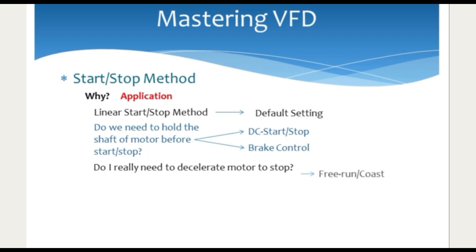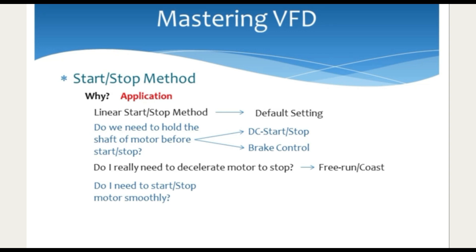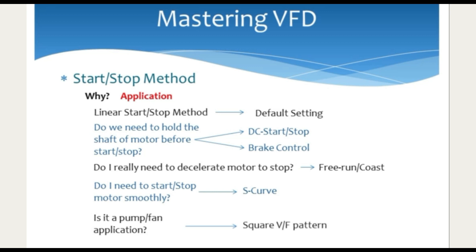Or if we need to decelerate the motor to zero speed, we select free run or coast method. For an elevator application where smooth start and smooth stop is required, we can select S-curve. If the application is a pump or fan, at low speed we may require less voltage, so we can choose the square V over F pattern. We will check all these practically in upcoming videos.